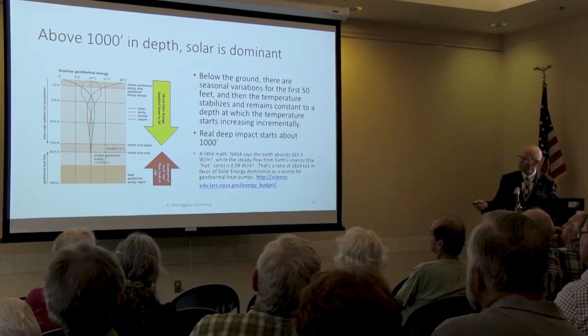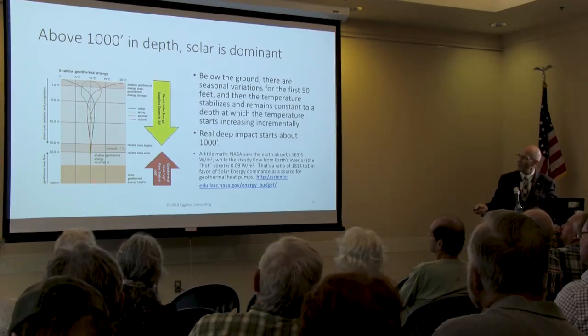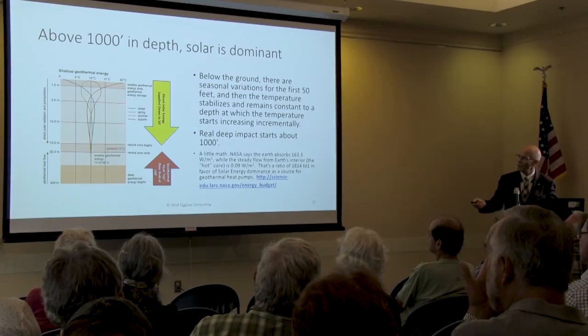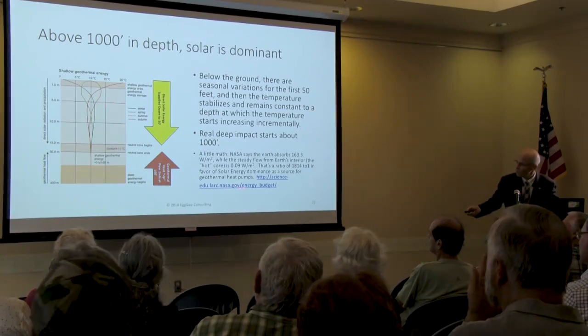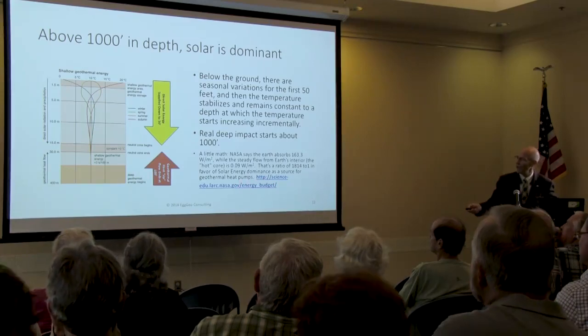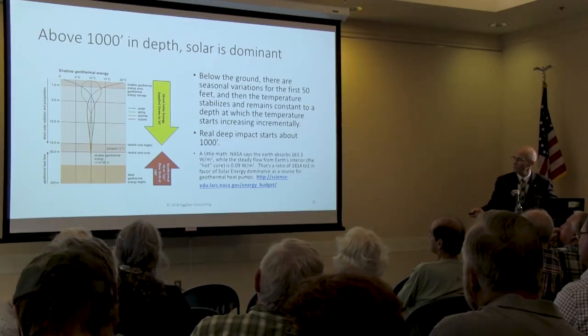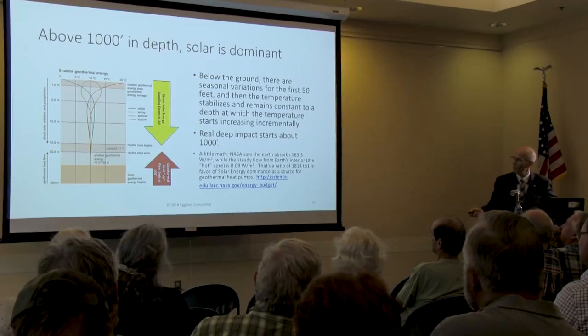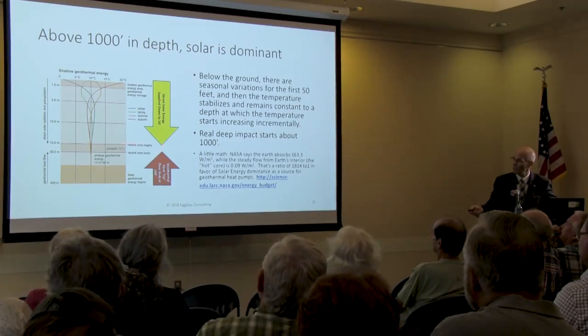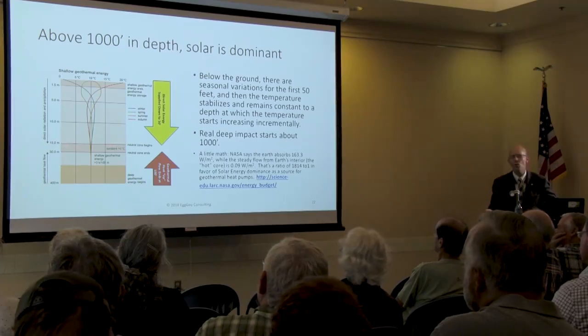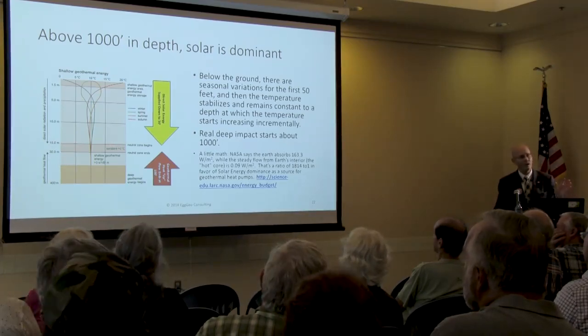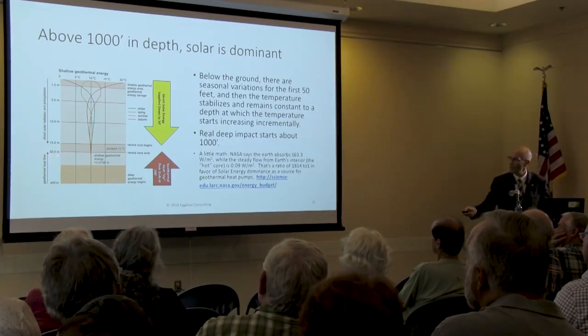And this is just one more technical slide. This is an actual chart that I got from a European Heat Pump Association or European Geological Association. I am going to share this slide presentation, and I'm sure Brian will get it to those who want it. But the solar inputs down to 45 feet are 100%. You can't even sense any of the radioactive decay of the Earth. When you get down to about 100 feet, you start to sense a little bit of the radioactive decay coming up. But until you get to 1,000 feet deep, it's almost not measurable.